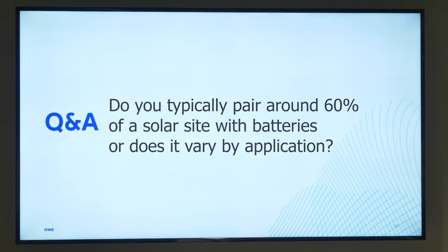Typically we're looking at a minimum of 25% in order to be able to do effective peak shaving, or load shifting. The minimum size is probably around 25% as a rule of thumb for the industry. The upper limit is really just seeing if there's a market for it in terms of oversizing a battery, going 1-to-1 scale, or maybe going at least around 50%. So the upper limit really depends on the location and the application.